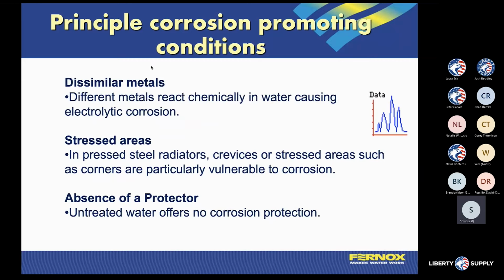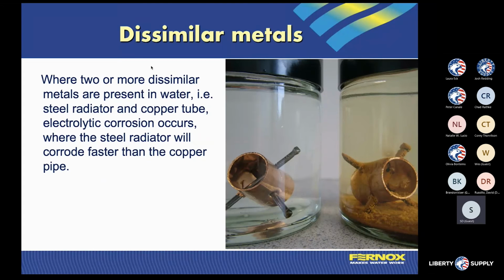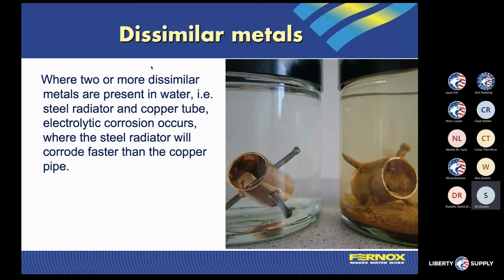We may have perfect water going into the system, but by the time we put it through these different metals and deal with all these other chemicals and pollutants that are in the system, we're going to eventually have to deal with the fact that the water is not going to be perfect any longer. So with the dissimilar metals, we do need some kind of inhibitor to maintain its integrity for the duration. We need to make sure that sediment and corrosion do not happen from the inside out.